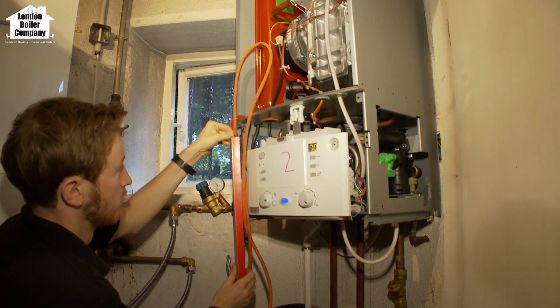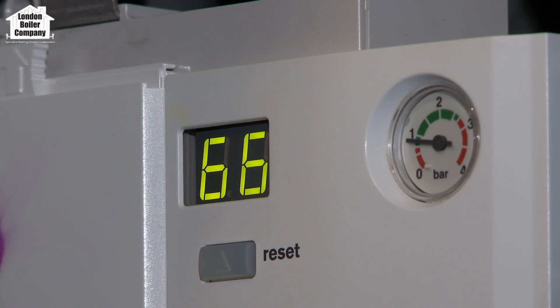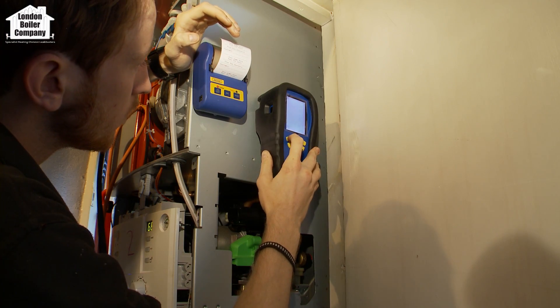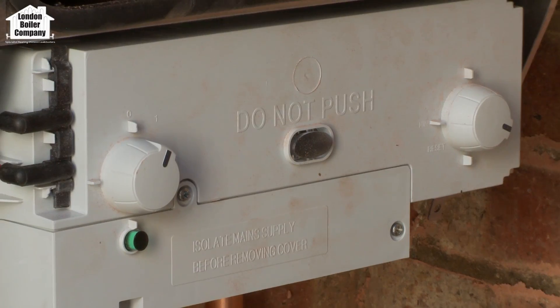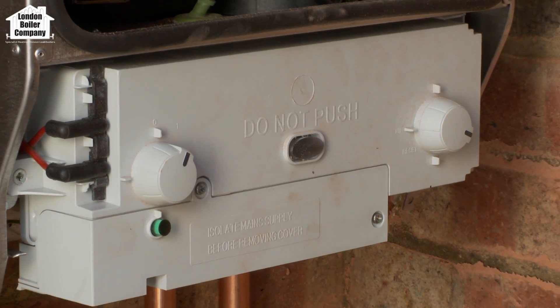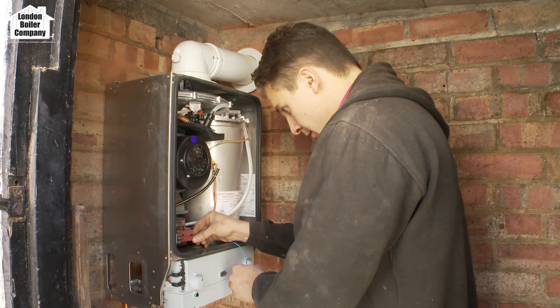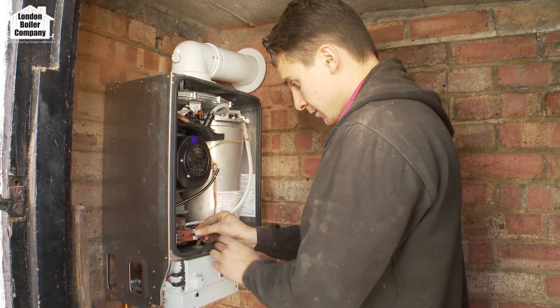So that really does need to be dealt with — it needs to be treated appropriately. On every boiler that we install, one of the first things we do is test the water. One of the most important things from the boiler manufacturer's perspective, purely for the warranty, is that the water in the central heating system is clean to the appropriate standard as required by the manufacturer.